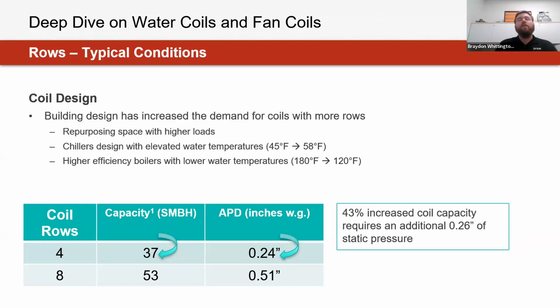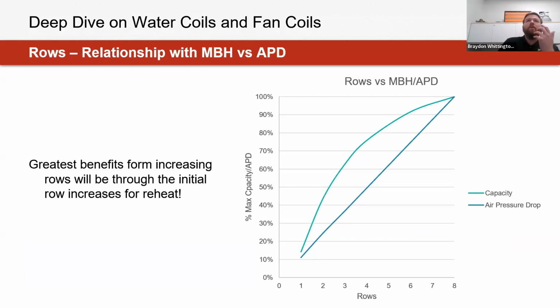And I started to dive into the weeds there too. I mentioned earlier evaluating the influence of increasing rows based off of the maximum amount of capacity that can be achieved from a coil versus how much additional pressure drop it's going to be adding. This graph is just a comparison of, as we increase rows of coil, how much of the maximum capacity of that coil we are achieving and how much additional air pressure drop we are adding. One interesting relationship when evaluating increasing rows versus capacity and pressure drop is that there is a more drastic increase in capacity between the first few rows of coil being added, while the pressure drop is more of a linear relationship, adding resistance on our casing.